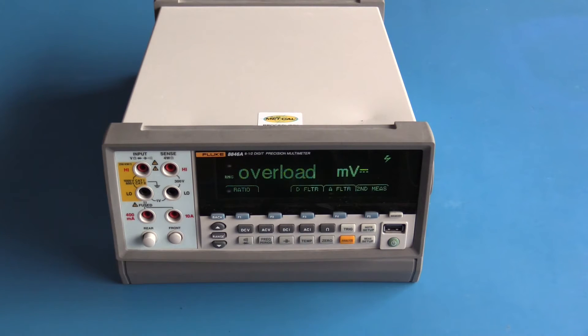To turn this meter on and off there is a power switch at the back of the meter that turns the meter completely off. Normally on a bench multimeter like this you do not ever turn the instrument off.